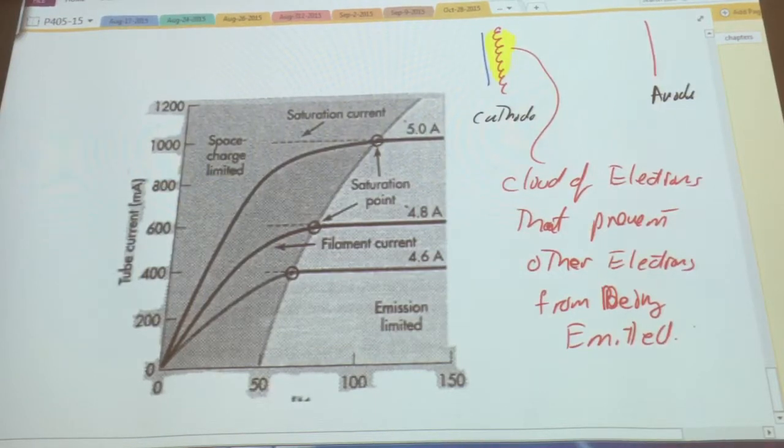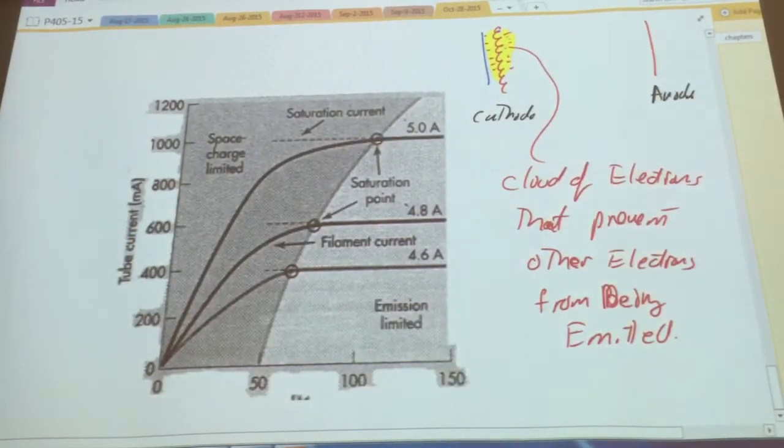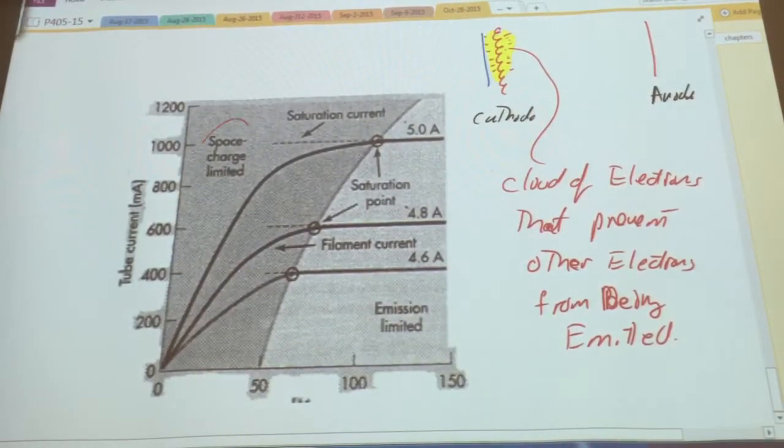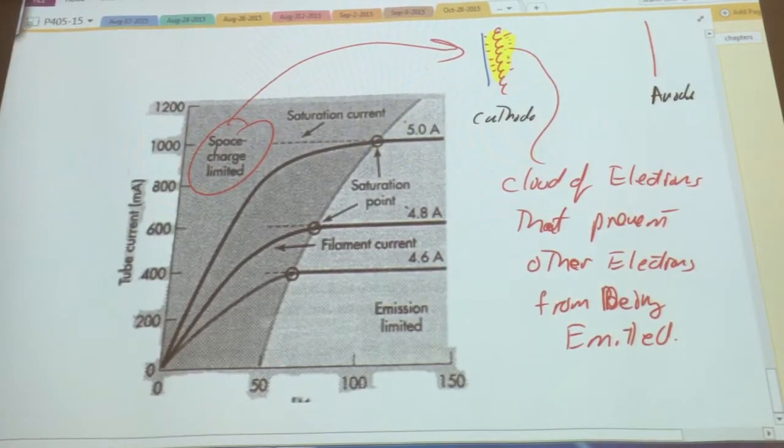So that is the bunch of electrons that have been emitted, and they hang around this cloud for a bit, not accelerated right away. That's why it happens at low KVP. And there is your space charge limited domain, and what's causing it.